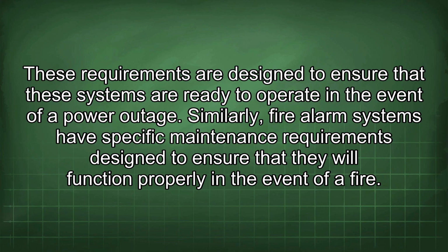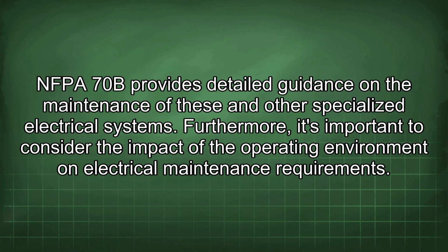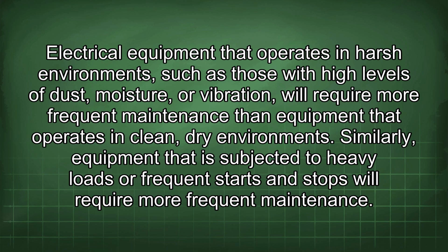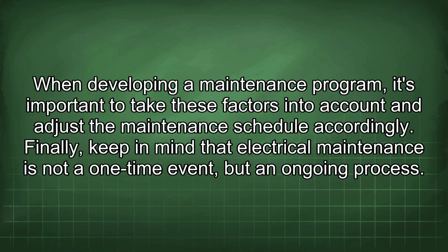Similarly, fire alarm systems have specific maintenance requirements designed to ensure that they will function properly in the event of a fire. NFPA 70B provides detailed guidance on the maintenance of these and other specialized electrical systems. Furthermore, it's important to consider the impact of the operating environment on electrical maintenance requirements. Electrical equipment that operates in harsh environments, such as those with high levels of dust, moisture, or vibration, will require more frequent maintenance than equipment that operates in clean, dry environments. Similarly, equipment that is subjected to heavy loads or frequent starts and stops will require more frequent maintenance. When developing a maintenance program, it's important to take these factors into account and adjust the maintenance schedule accordingly.